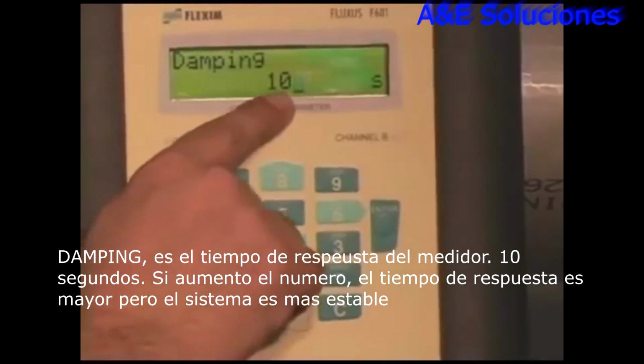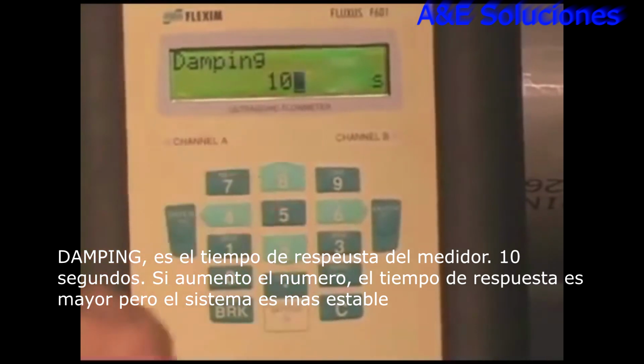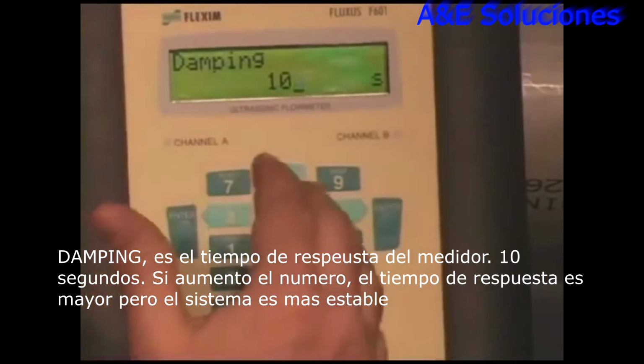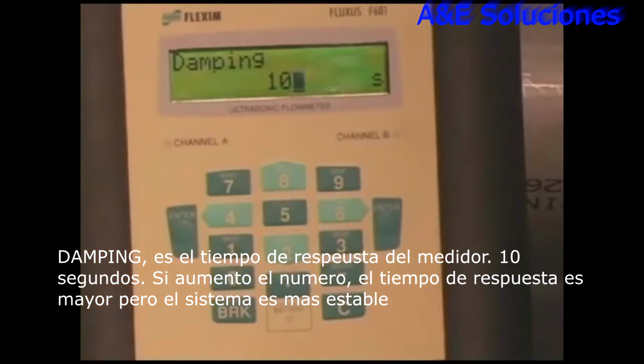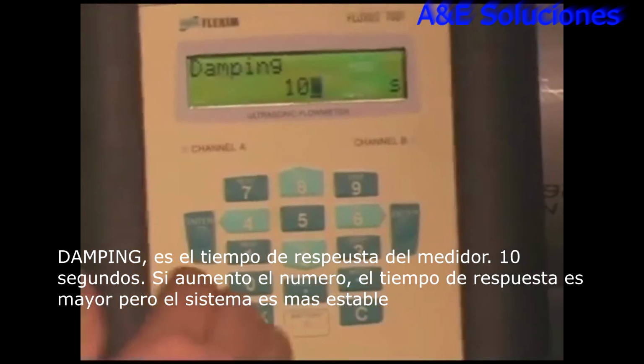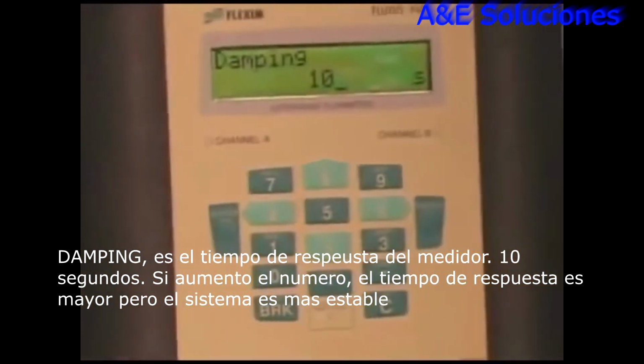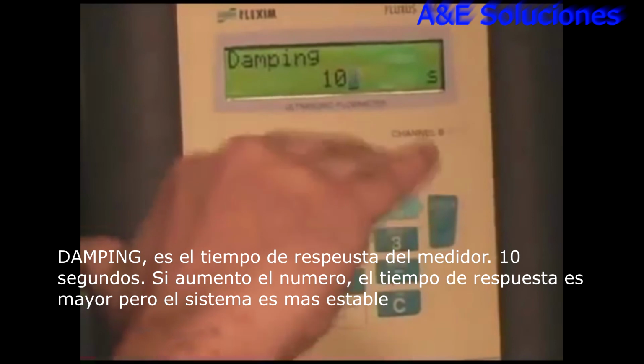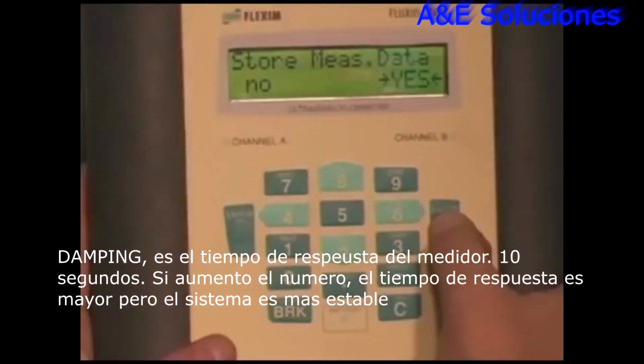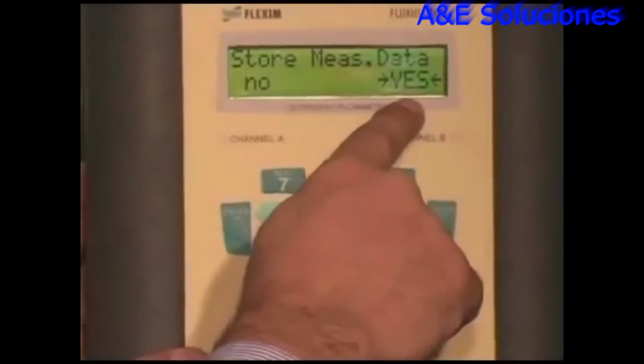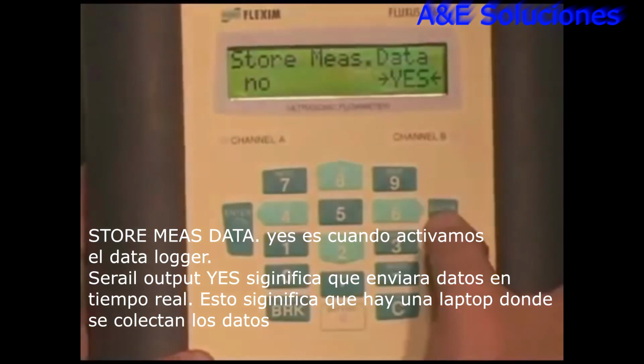Dampening setting, that's the response time of the meter. 10 seconds means it takes 10 seconds to ramp up to the flow rate. The trade-off there is response time versus stability. So if I choose a larger number, the response time will be slow, but the meter will be more stable. Store measured data, yes. This is where we turn on our data logger.